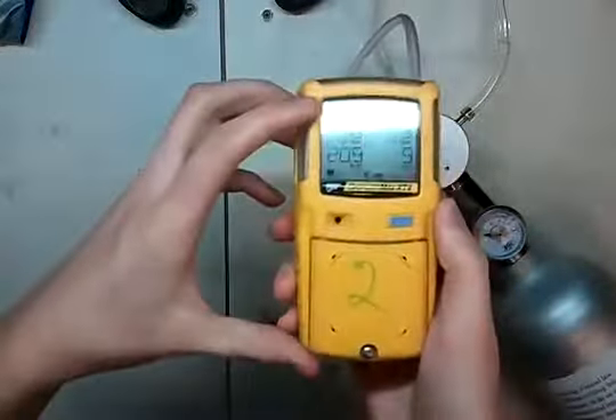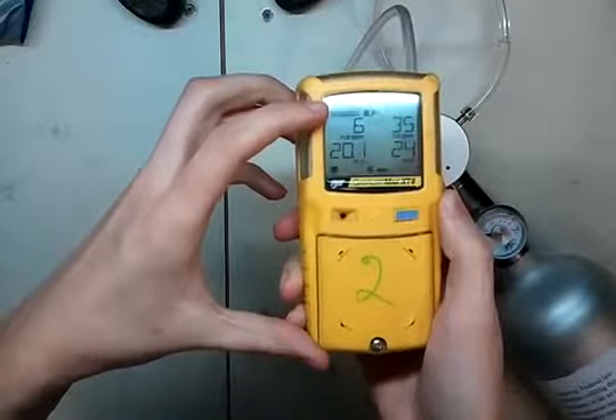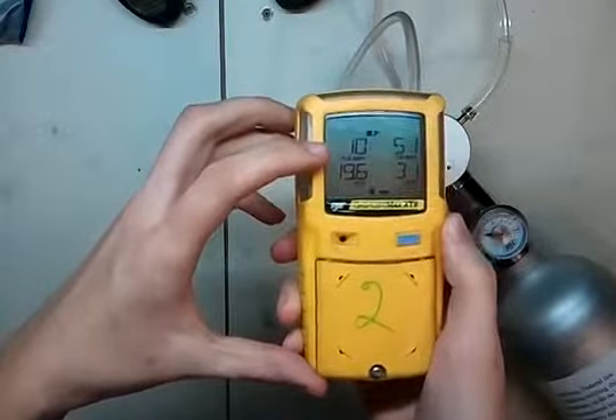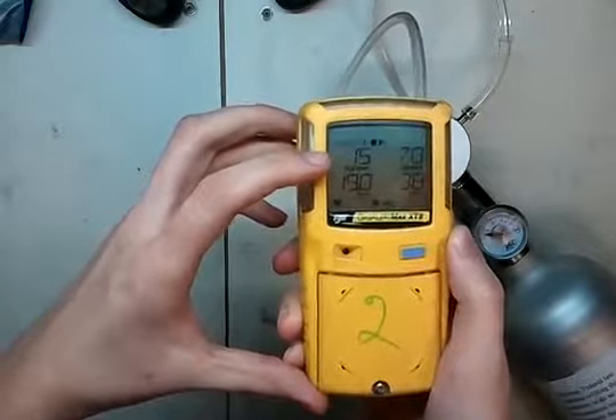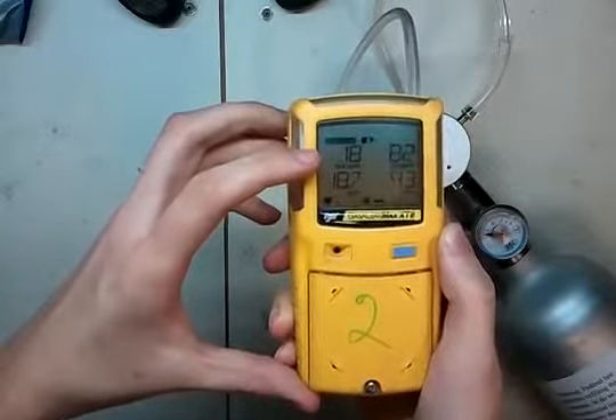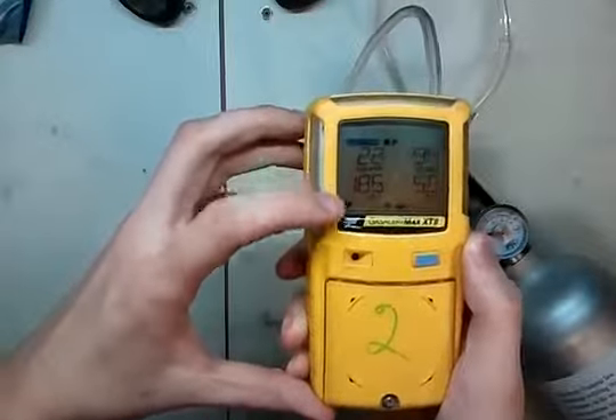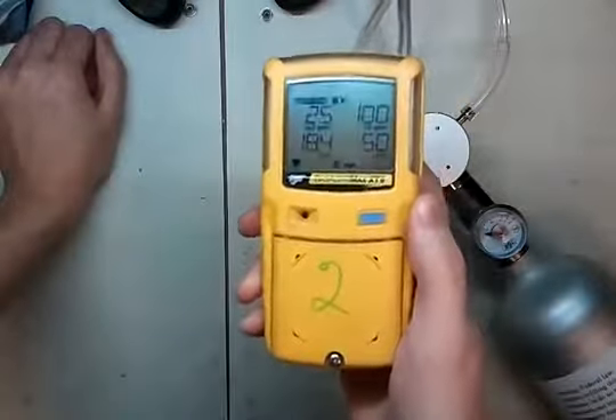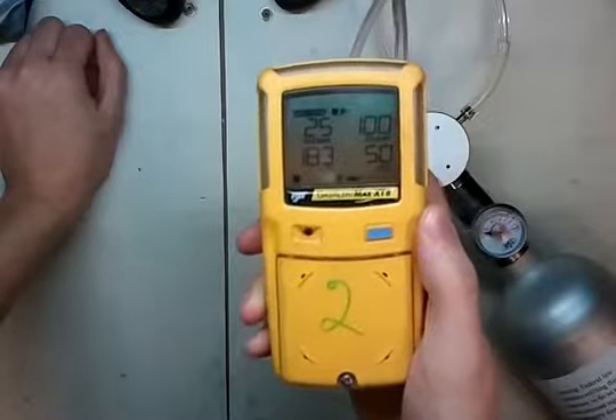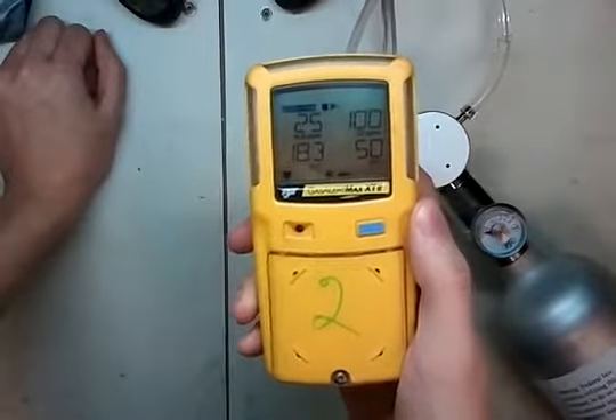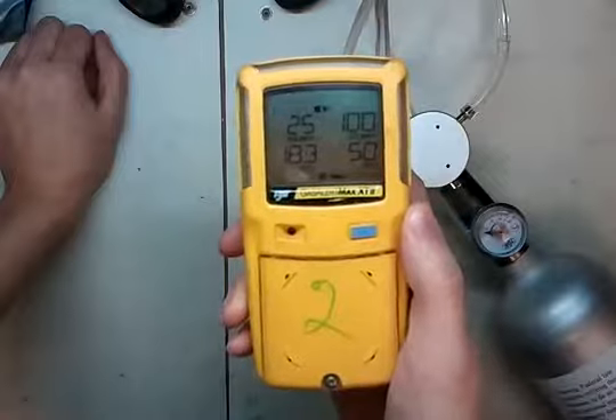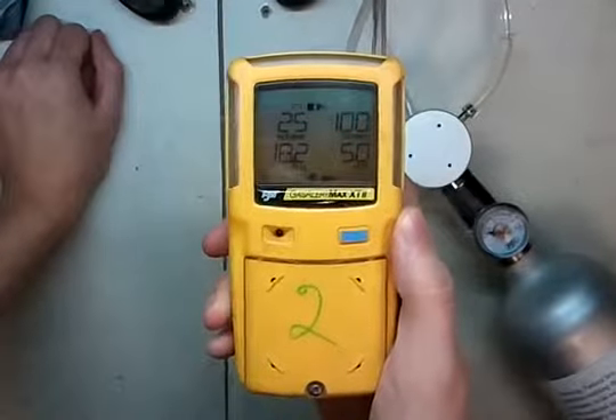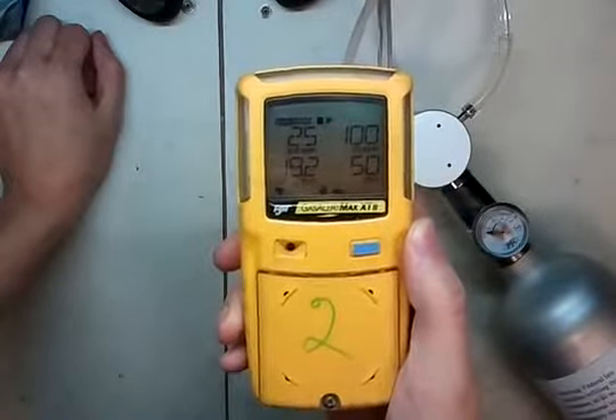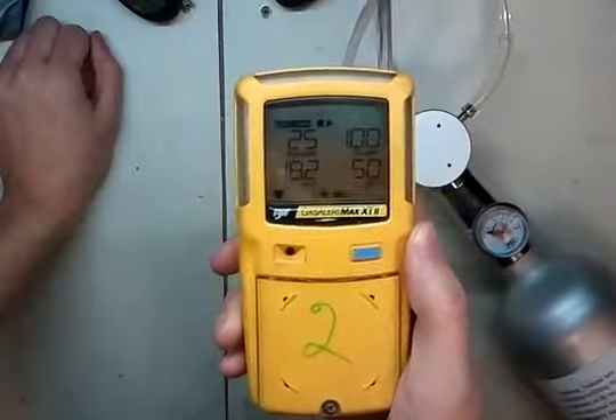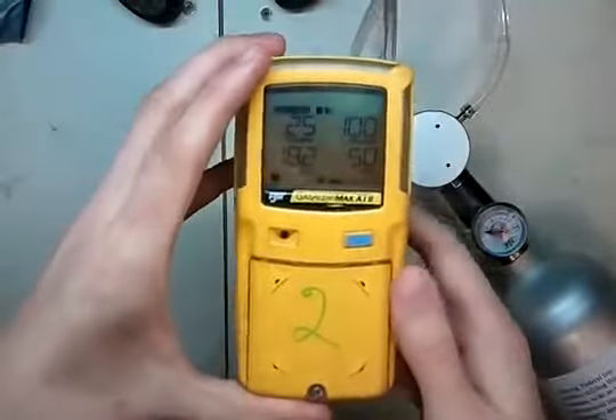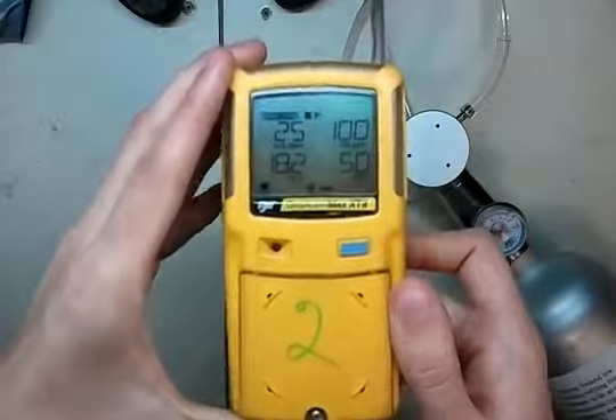Now if you watch, it says auto span up in the corner here, and now we'll start getting gas values. Remember, this one is 25 parts H2S, 100 parts CO, 50% LEL methane, and 18% oxygen. The oxygen is never going to be exact. It's always the most inaccurate sensor because it's a one-point calibration. So if it's close, that's good. Okay, now you'll see us taking the calibration values in there, and it's going to hold that for a while to make sure that the sensors are stable. So while that's going, you can just kind of set it down to the side.